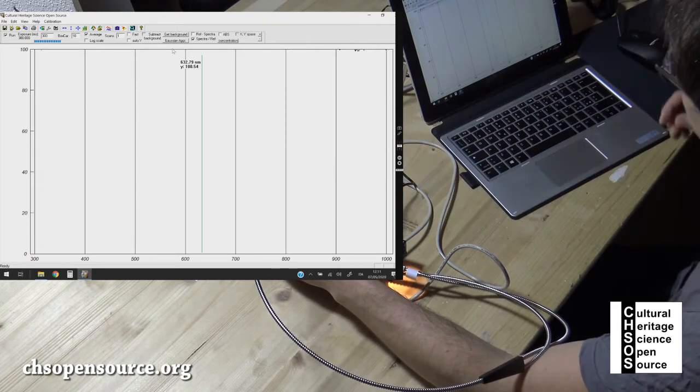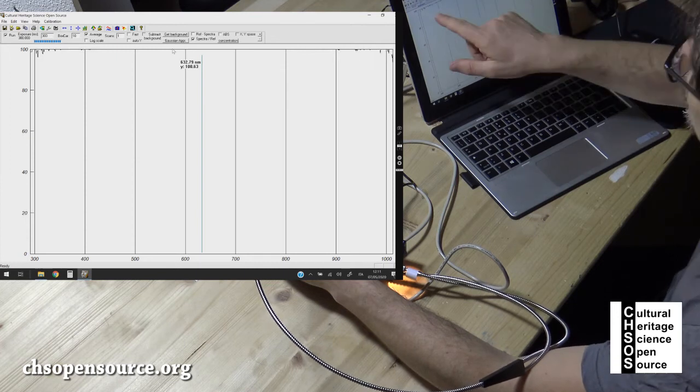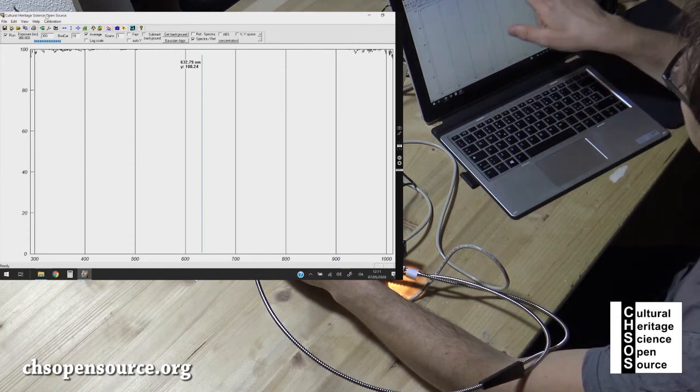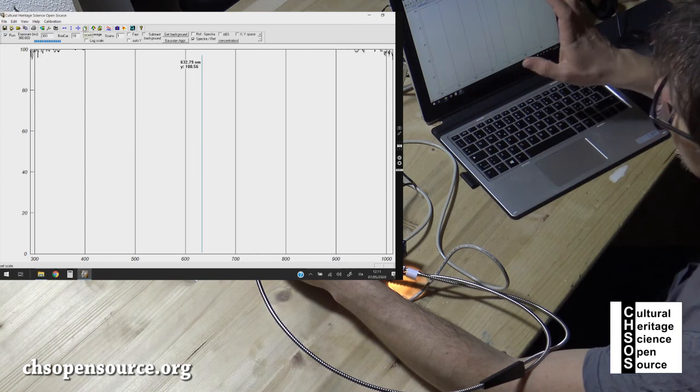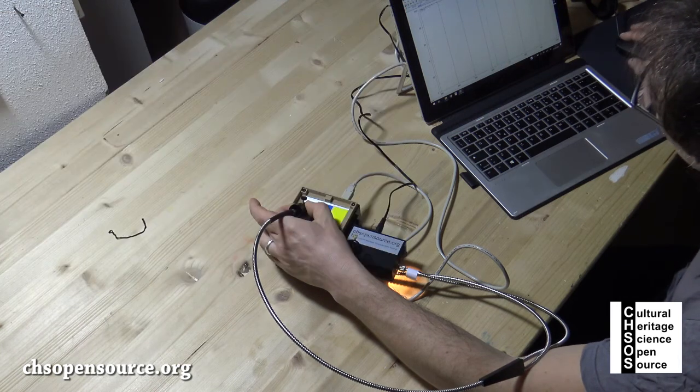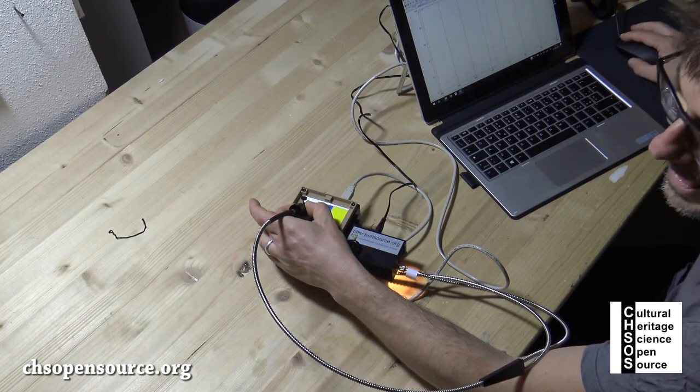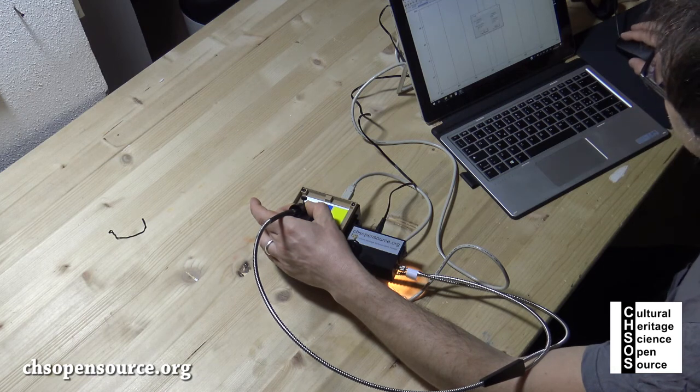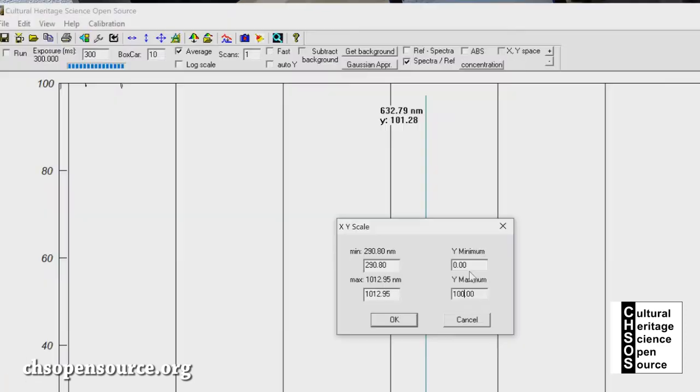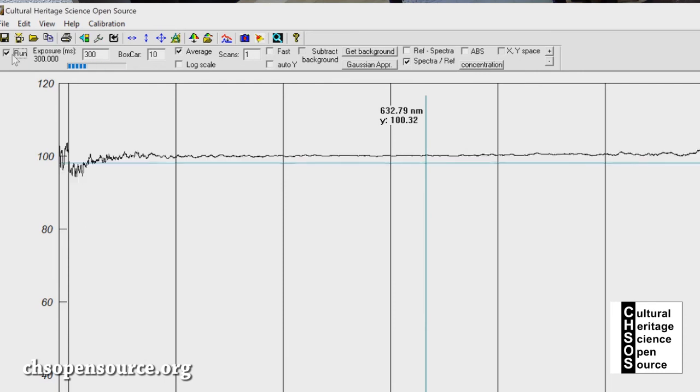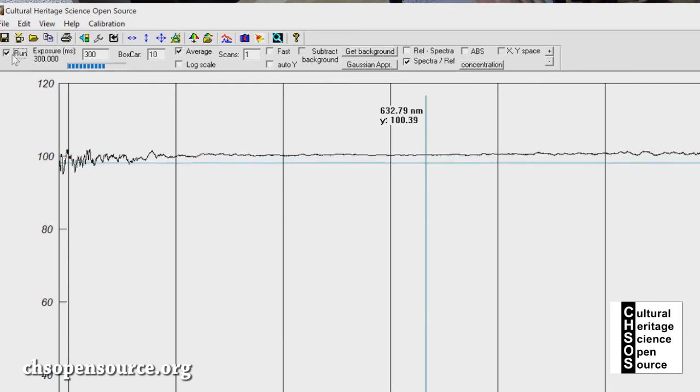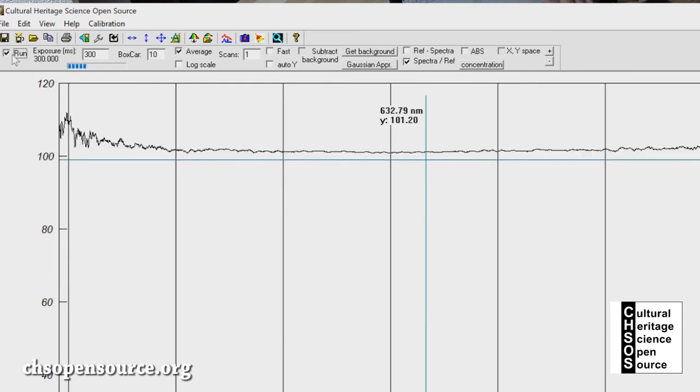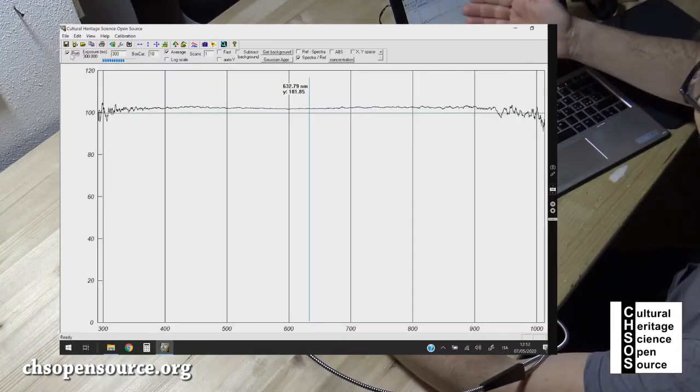We can start to do our examination. Just to check the system over here we have three, four colors. We have blue. This is the reflectance spectrum of the blue, so the system is working. We already have saved this spectrum. I use it as a reference to check everything is working. I can move on the yellow, and I can move on the red. The system is working and has been calibrated.